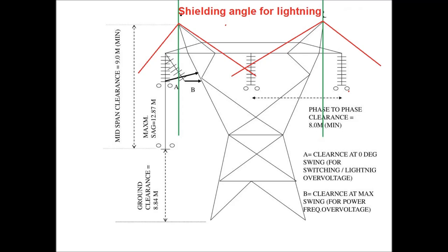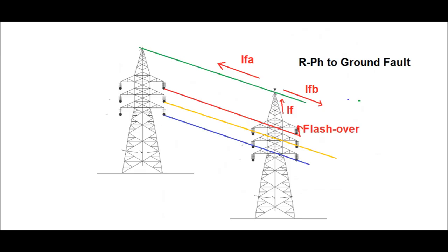Normally the shielding angle varies from 25 to 30 degrees. What is the purpose of the earth wire besides protecting from direct lightning to the phase conductors? It provides the return path for any earth fault occurring in any phase.